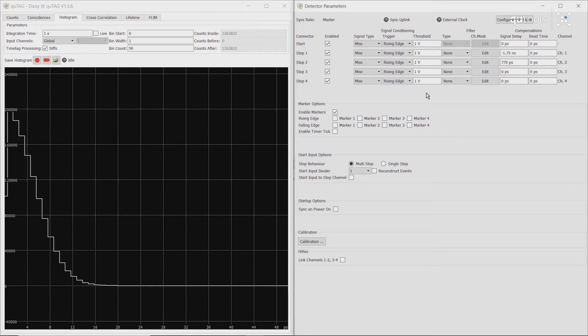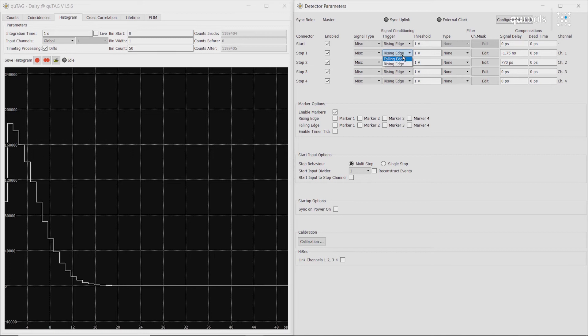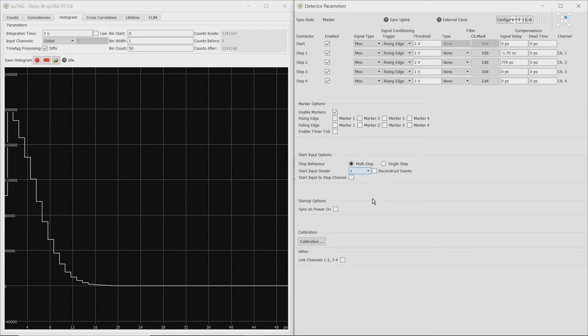In the detector parameters panel, we can do all sorts of other options. Including changing whether to trigger on the rising or falling edge of the signal. And then various delays. Whether we want to put a divider on the channels. Whether we want to link the channels for higher resolution, calibration, and more.